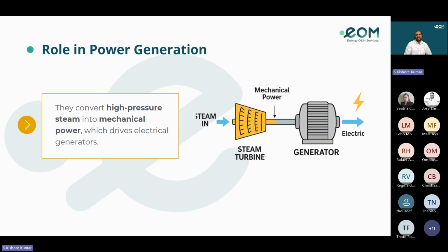In combined cycle power plants, steam turbines operate with gas turbines to enhance efficiency. Because of their high power output, capable of generating hundreds to thousands of megawatts, they are also suitable for baseload generation, providing constant power to the grid. Steam turbines provide high efficiency in combined systems, versatility of heat sources, and grid stability as a synchronous machine. They contribute to inertia, frequency regulation, and voltage stability.